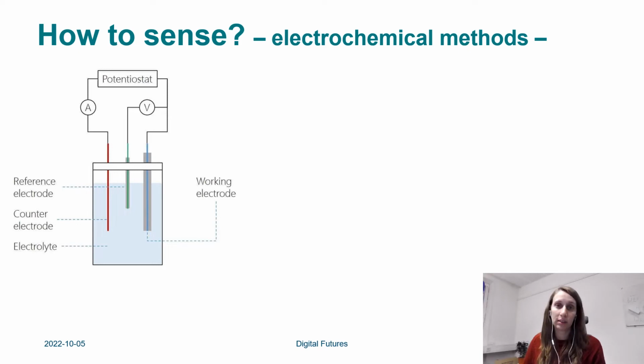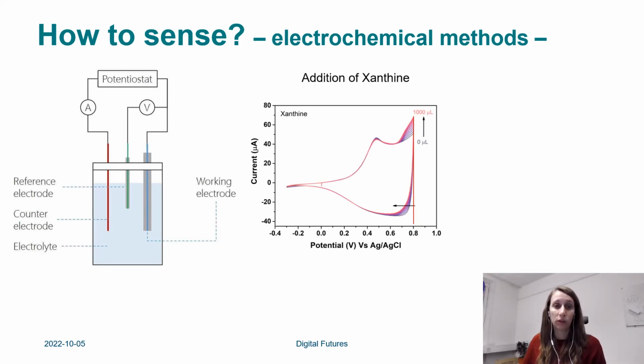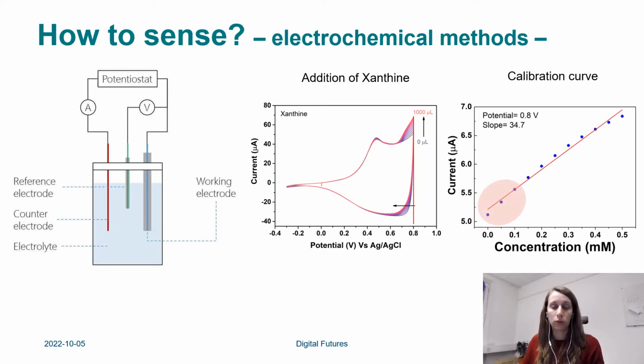And we did some studies where we added increasing amount of xanthine, and we tested the response on the sensor current. And we saw that at potential between 0.7 and 0.8 volt, we have a change, which can then be plotted to form a calibration curve. So the calibration curve tells us basically how the sensor change for increasing concentration of xanthine, but also for this particular kind of analyte, what we need is sub-micromolar concentration. So we want to move towards device geometry that is portable, can be integrated in packaging, but it's also sensitive enough to measure at very, very low concentrations.